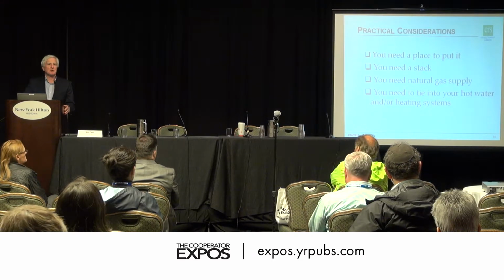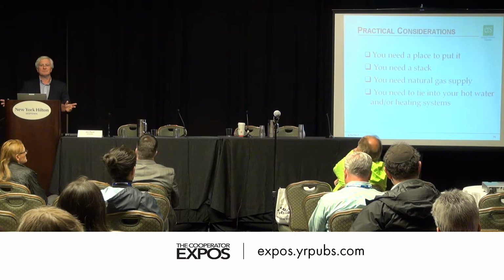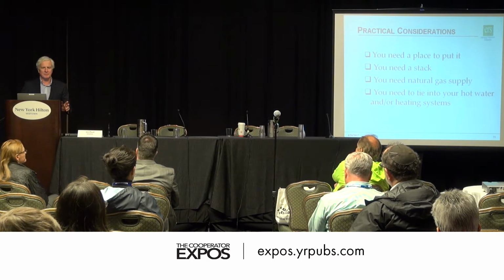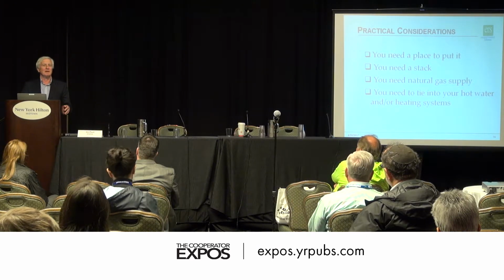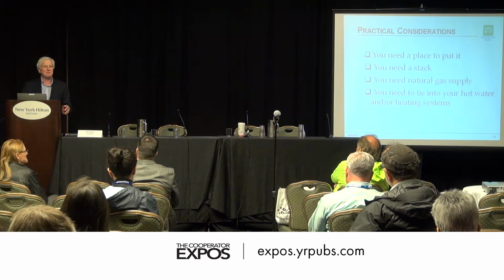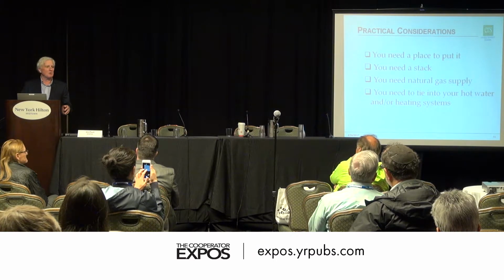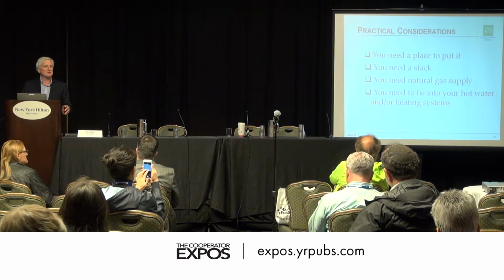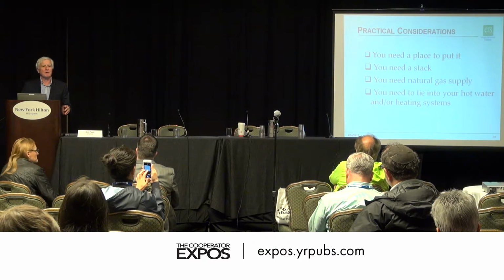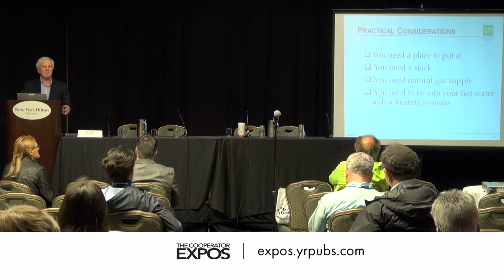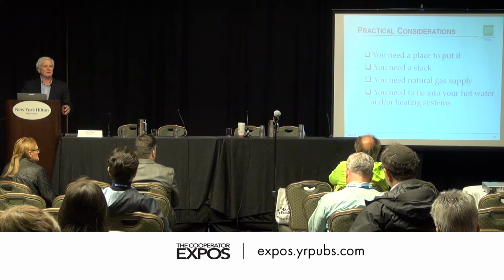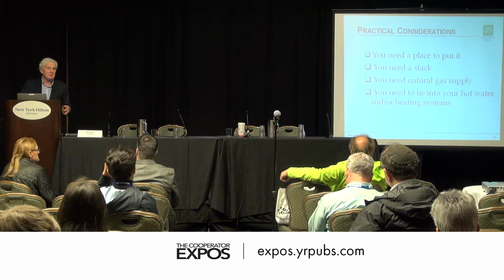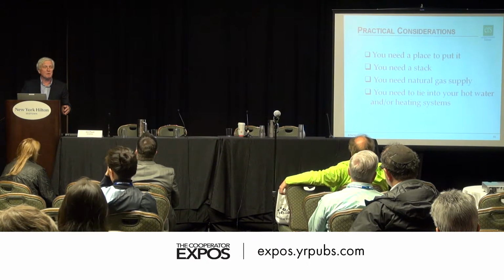So what are some of the practical considerations of putting in a CHP system? First, you've got to find a place to put it. Most of these are retrofits, and it can sometimes be challenging to find a place. Typically you like to find a spot near a boiler room, or where the natural gas line comes in, or where the hot water piping is. Fortunately, in many boiler rooms there might be some room, or a room next to the boiler room.